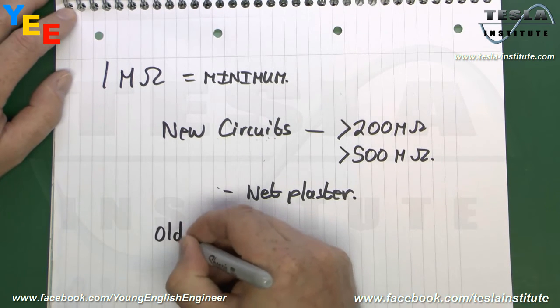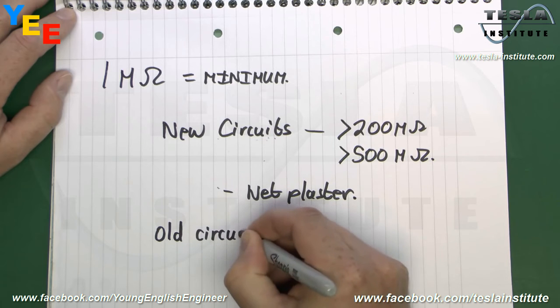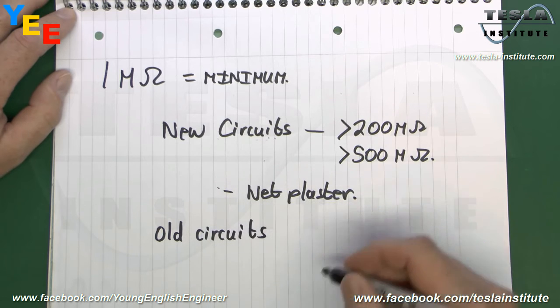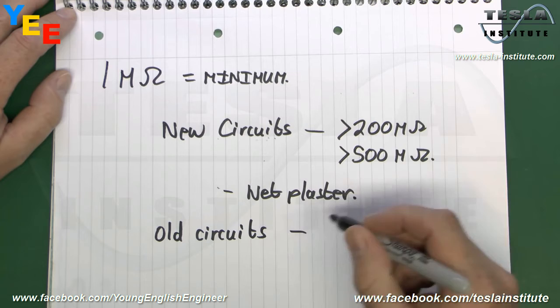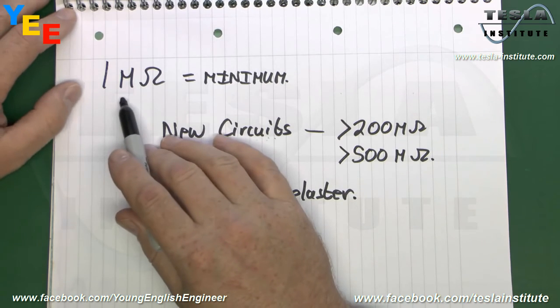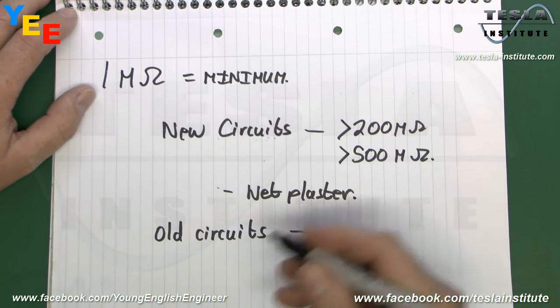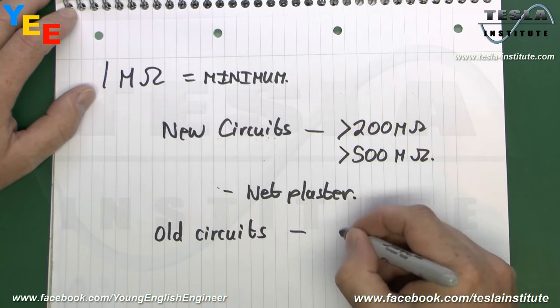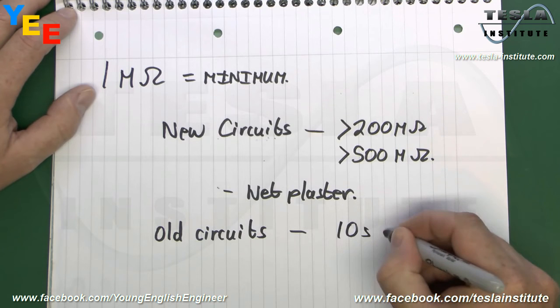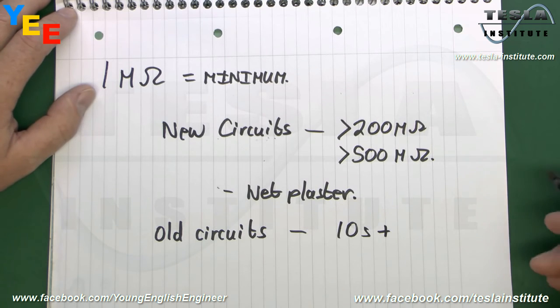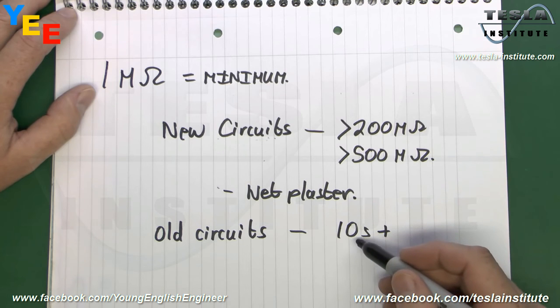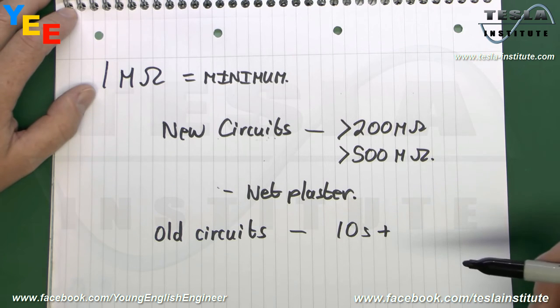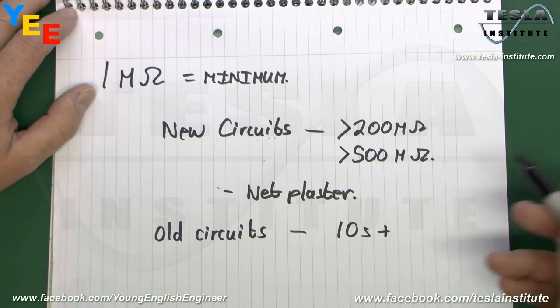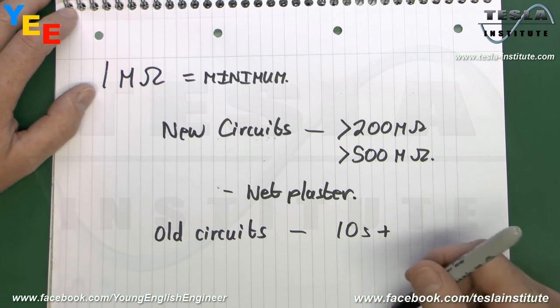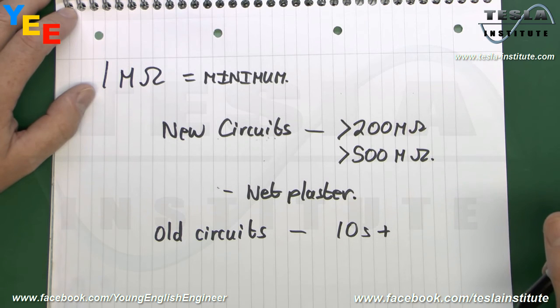Now, old circuits, on the other hand, can be all kinds of values depending on how old they are and what sort of state they're in. But again, 1 megohm really is absolutely useless. You should be seeing considerably more than that. As a rough guide, you should be seeing in the tens plus range. Anything less than, say, 10 or so would certainly require further investigation, and it's not uncommon to see old circuits in the range of say 50 or 100, that kind of area.